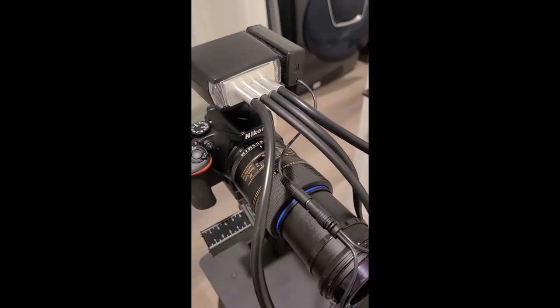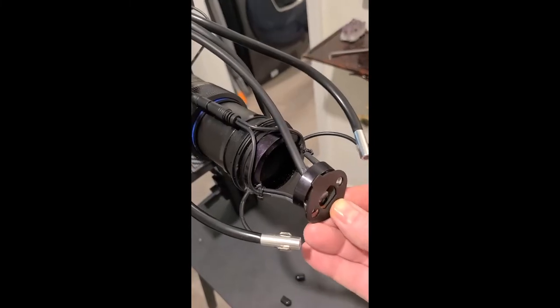For the center and side lighting options: if you're going to take side-light images, there are two little caps that come off, which allows light to come out and light the side of the irides. There is also a little plate that covers up two fiber optics. When the flash fires, light comes out of all of those fiber optics. This plate covers up those two center fiber optic openings.